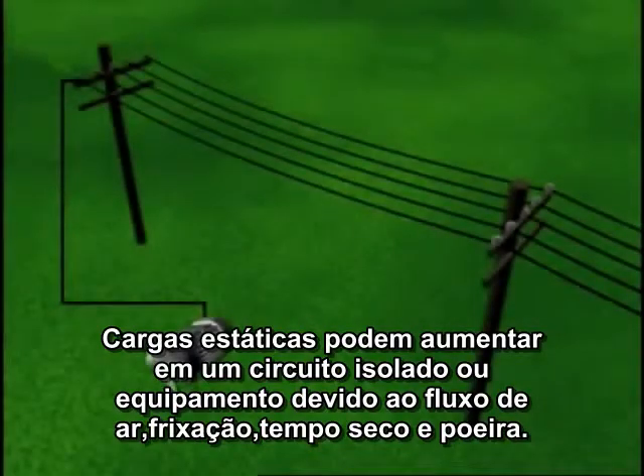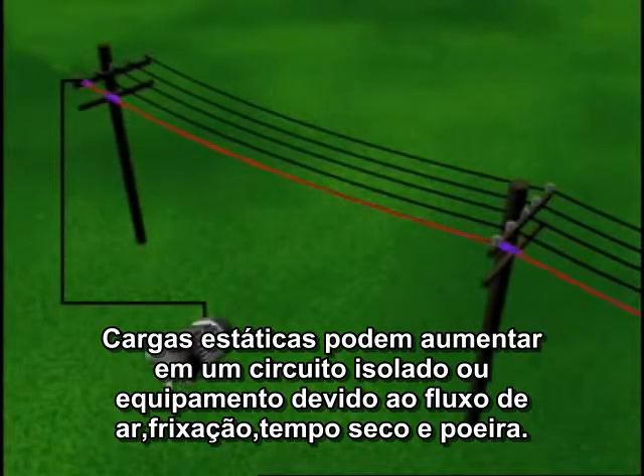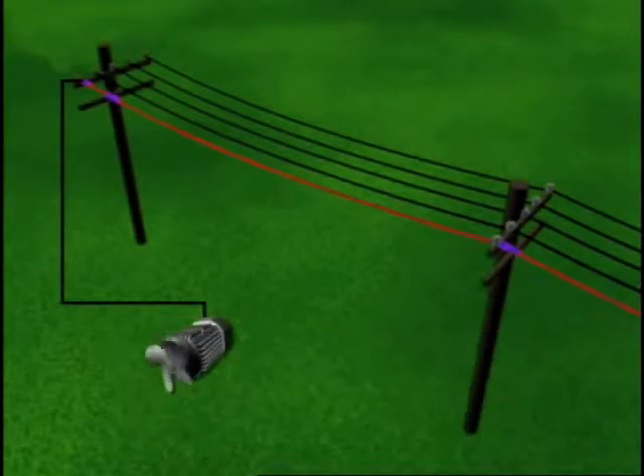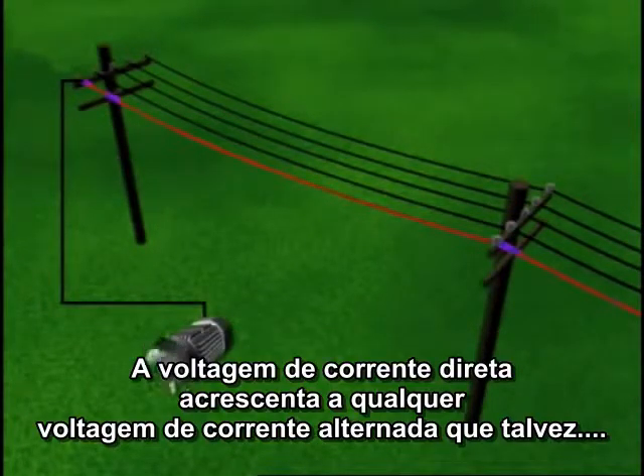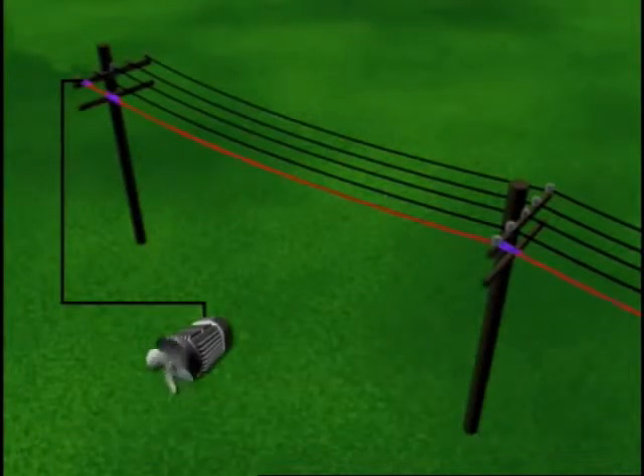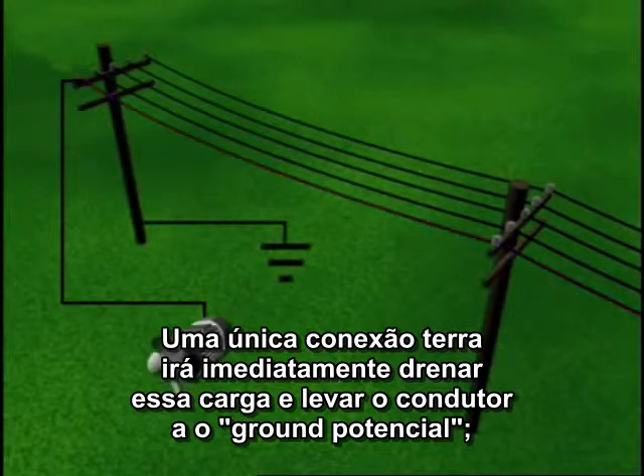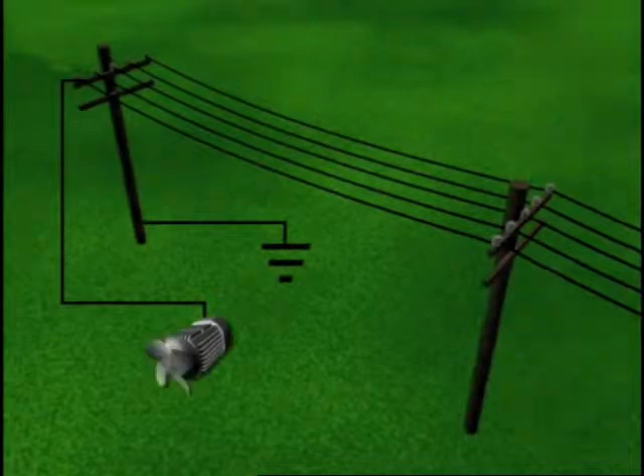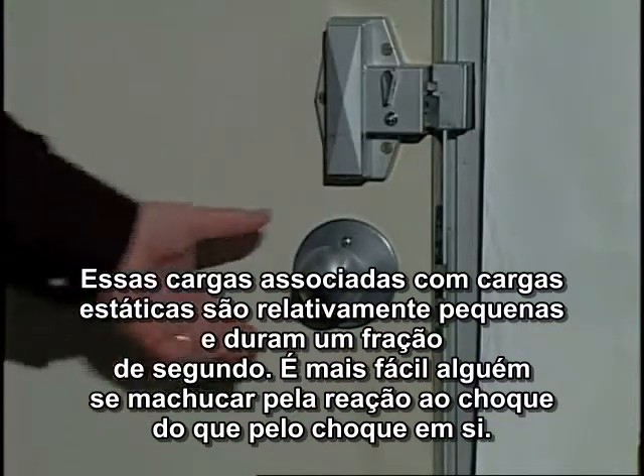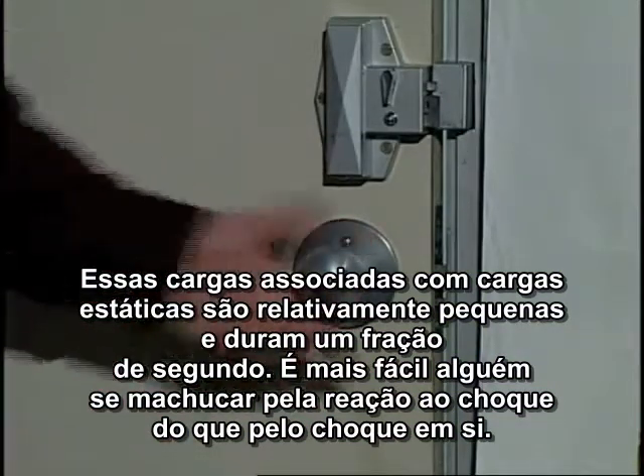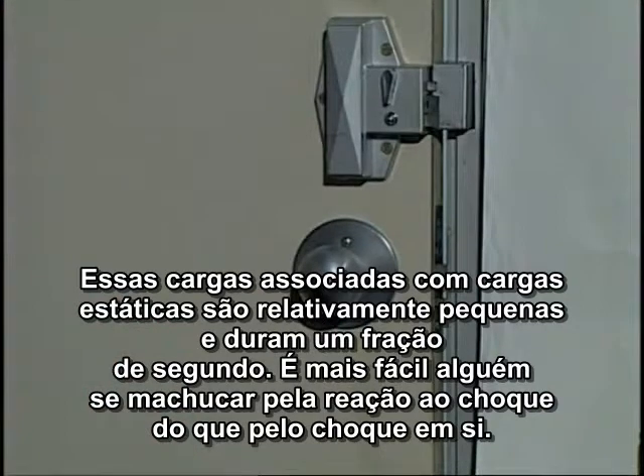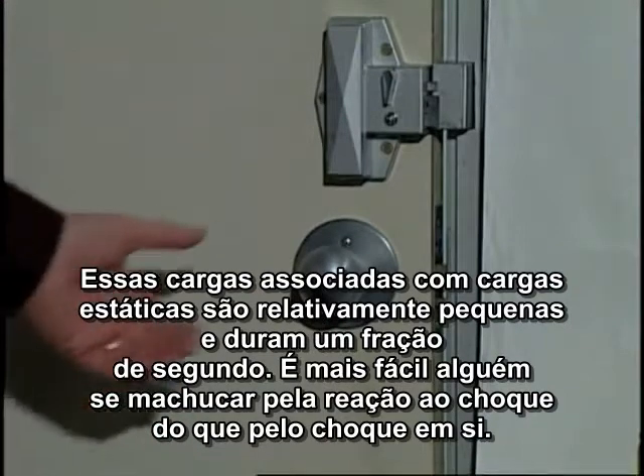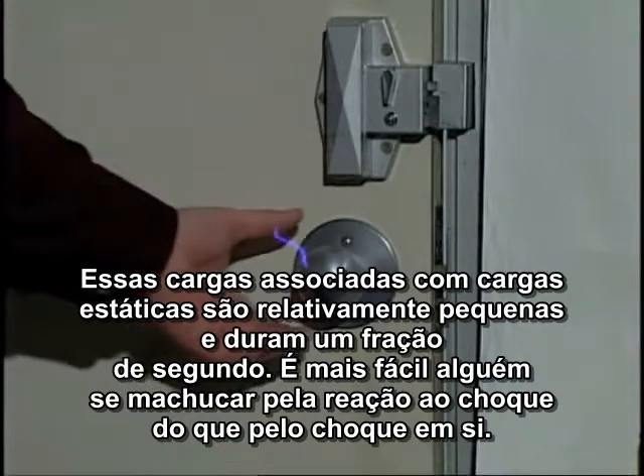Static charges can build up on an isolated circuit or equipment due to airflow, friction, dry conditions, and dust. The direct current voltage adds to any alternating current voltage that may be present. A single ground connection will immediately drain off this charge and bring the conductor to ground potential. Discharges associated with static charges are relatively small and last a fraction of a second. People are more likely to be injured from the reaction to the shock than by the shock itself.